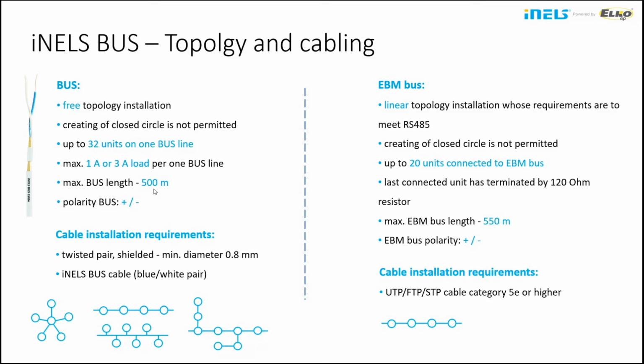We also use the EBM bus topology, which meets RS-485. Closed circle, star, or any other topology is not permitted, only a straight line. You can connect 20 units in the EBM bus, and the last connected unit should be terminated with a 120 ohm resistor. The maximum length possible is 550 meters. This is also a polarity-based bus, and you can use UTP cable for installation, with a twisted pair shielded cable of minimum diameter 0.8 mm.